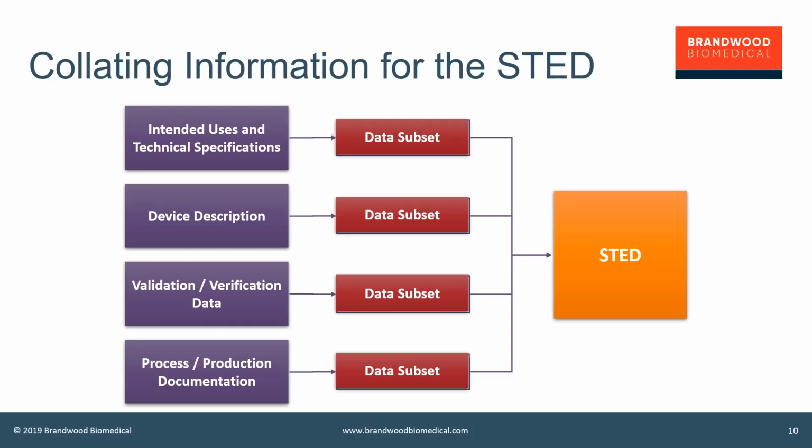Again, because there's some interpretation and it's all based on your risk assessment as to what you need to verify and validate, that's why the regulators spend most of their time looking at this section of the STED. And it's important to know that you need to include enough information that a regulator can come away from reviewing that set of data between your verification and validation data to say, yes, I believe that the company, the manufacturer, has proven the safety and effectiveness of this device has been met.